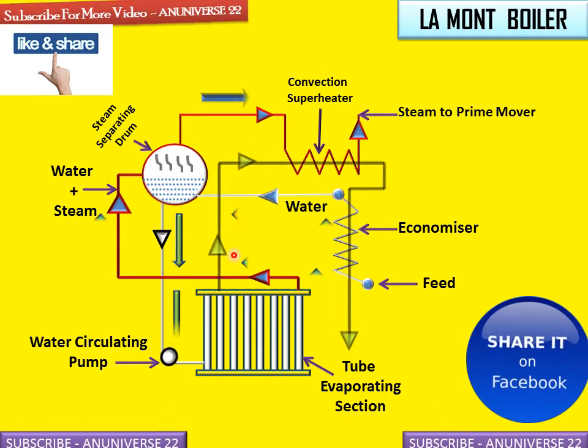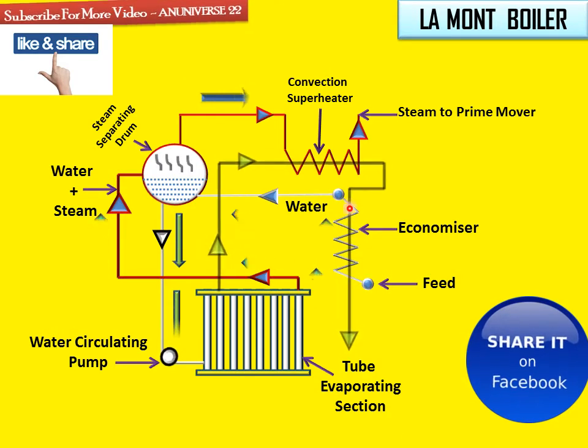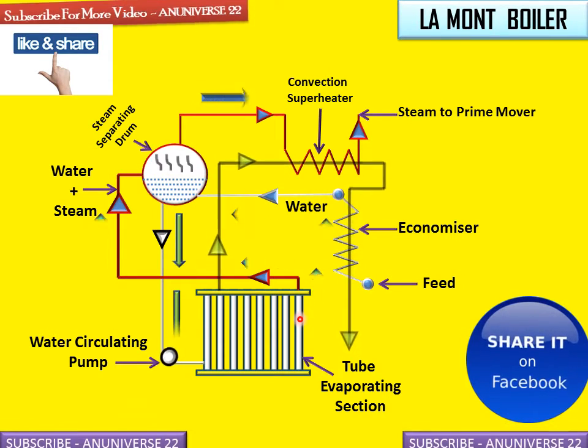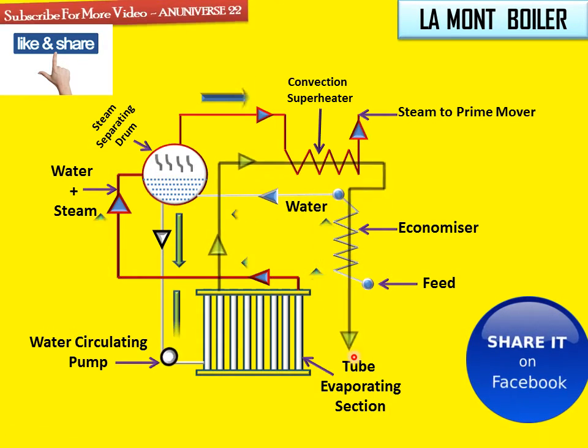To repeat the working cycle: water is supplied from the feed pump to the economizer, where it is heated by the combustion flue gases. It is then supplied to the steam separator drum. In the drum, the water is separated and supplied to the centrifugal pump, where it is recirculated through the evaporating section. Inside the combustion chamber the temperature of the water increases and conversion of water into steam begins. The mixture of water plus steam returns to the separator, while the flue gases exit through the super heater, then the economizer, and then outside.